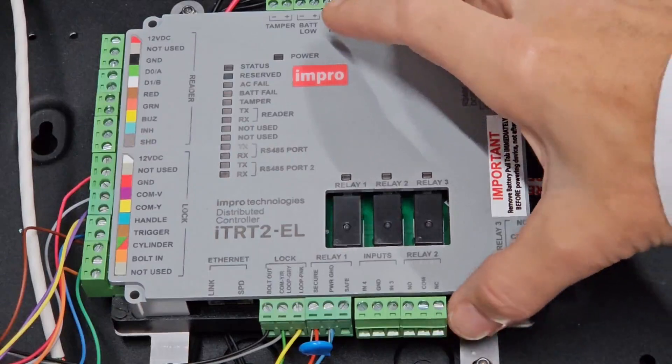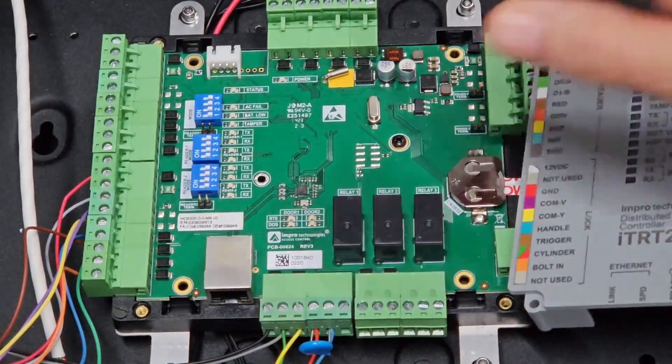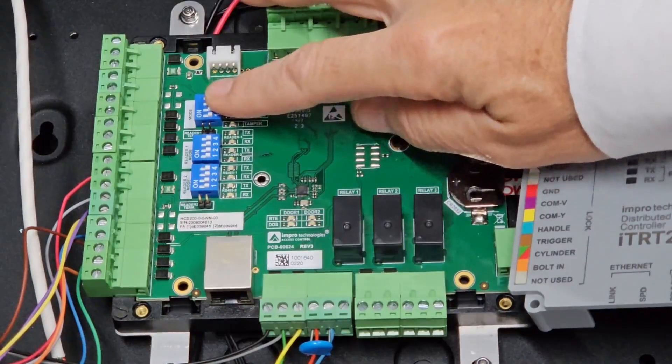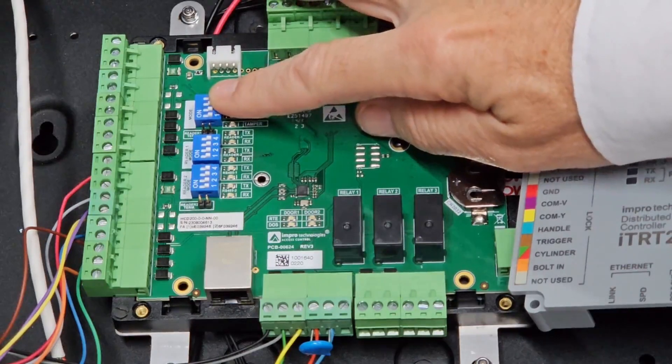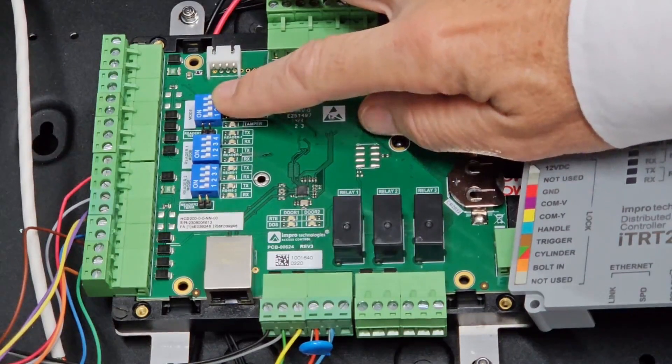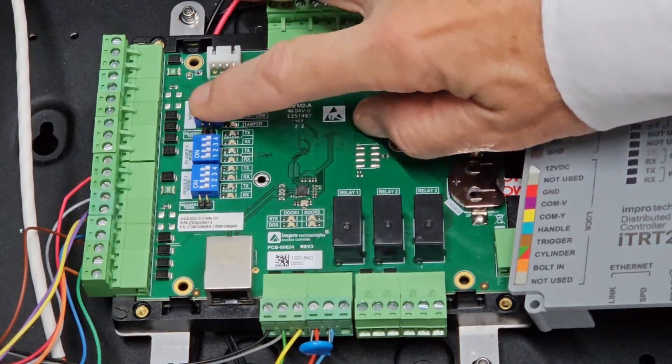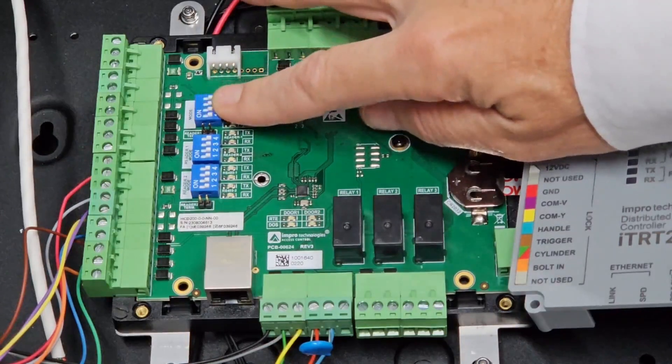Running through the DIP switch settings. The mode DIP switch must be set to 0000, that's all switches off. This is the door controller mode.